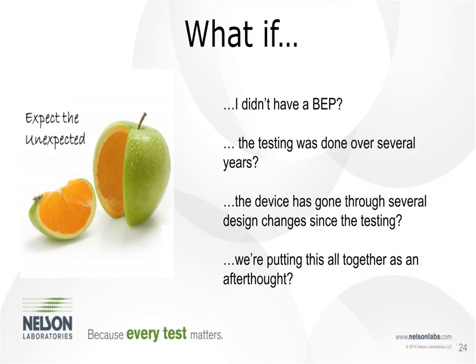What if the testing was done over several years? This has happened quite a bit, and what I recommend at this point is to not start with a BER, but start with a gap analysis where we can identify if anything is missing before we make a full conclusion about the device. So if the testing is done several years ago, or you're using a predicate where the testing was done several years ago, start with a gap analysis and decide if that testing is still appropriate. And then if you find that it is, go ahead and write a conclusion report, like a biological evaluation report for those findings.